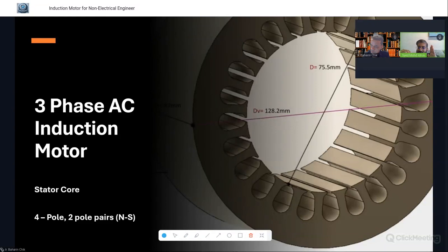Maybe the question is about the relationship between the power and the speed for VFD application. There is no relation, because when you size the motors, it is more on the kilowatts. For the RPM, the range is from 0 to 60 hertz. For example, if the power supply is 60 hertz, it goes up until 60 hertz. If it is 50 hertz, it goes up until 50 hertz only. But the power is a separate thing. It is not related to the RPM. You have some power rating of the motors, and then you can also control it by varying the speed.